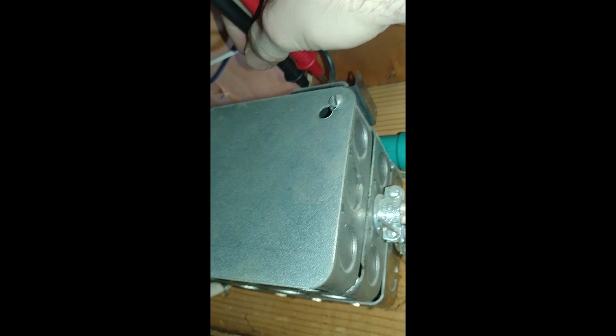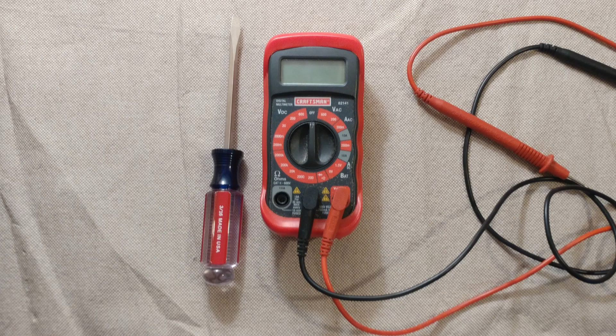In this instance, 18.2 VAC is proper for the 16 VAC chime. If you have too low a voltage coming from your transformer, your device may not power on, may prevent setup, or may not work properly. If the voltage is too high, it could cause humming, buzzing, constant chiming, or static interference noise over the doorbell.